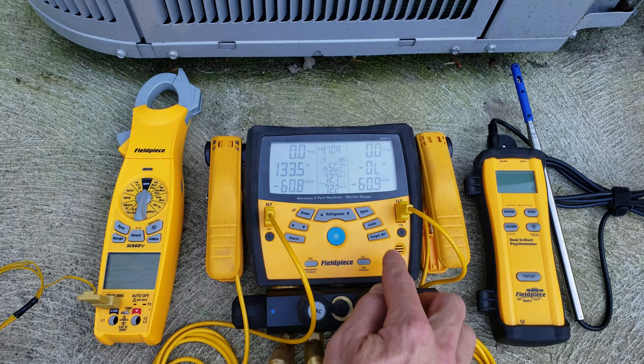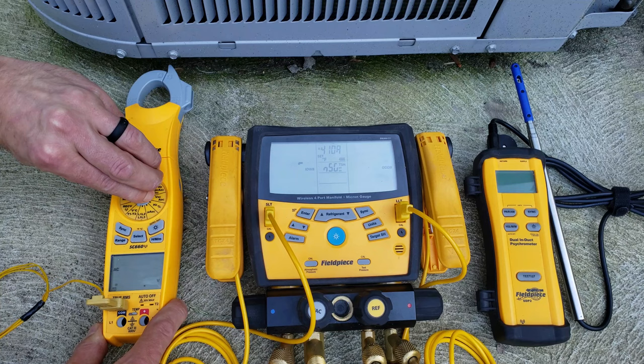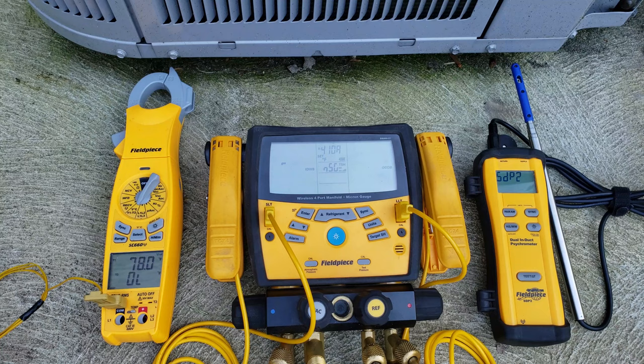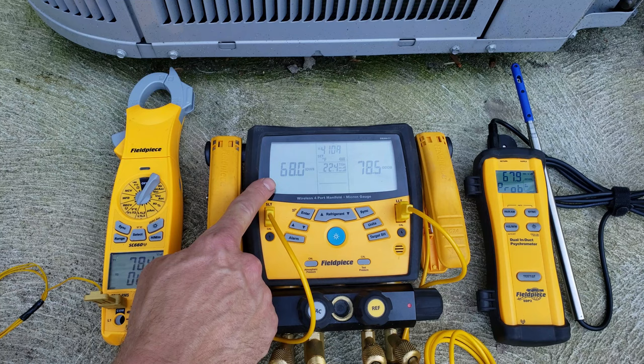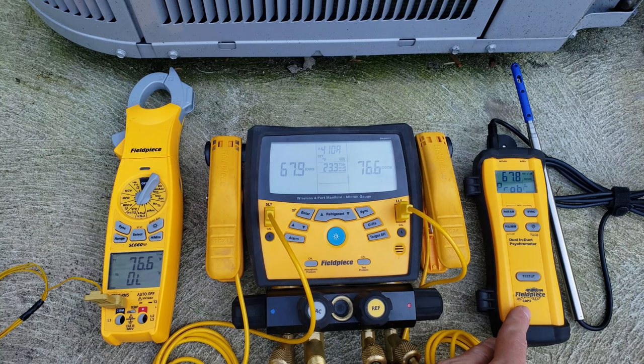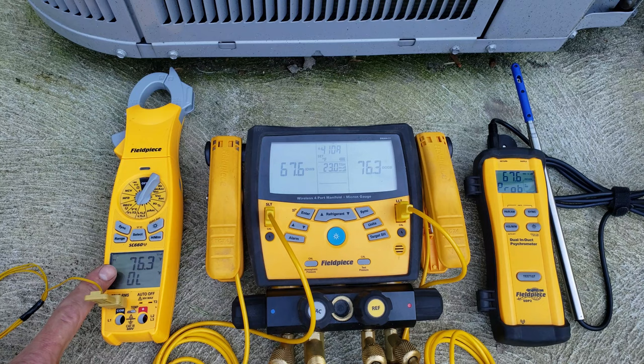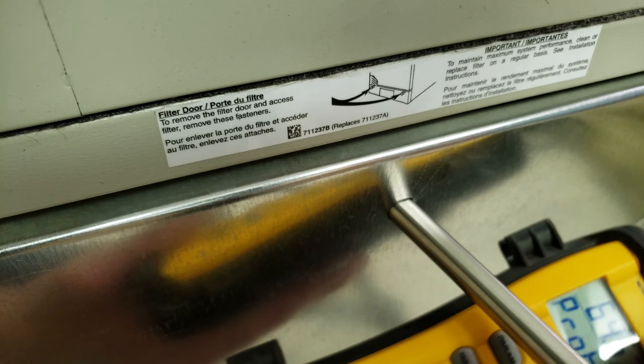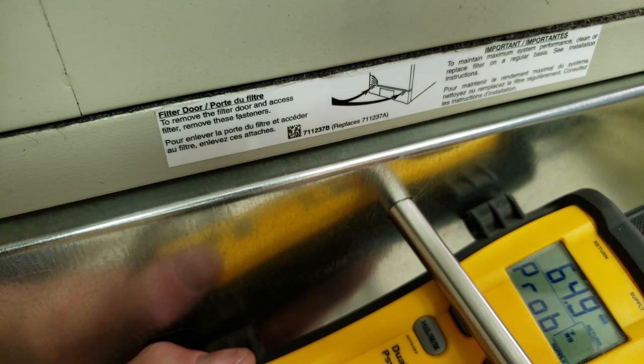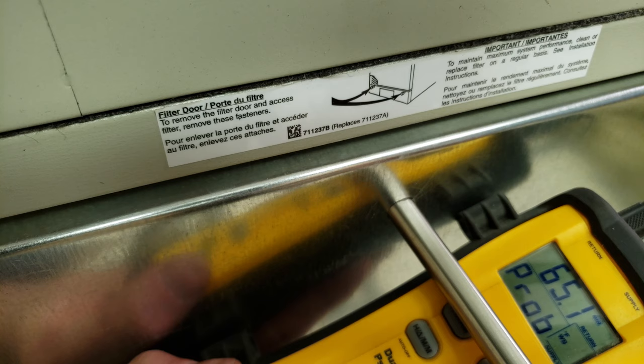Here we are outside with our digital manifold gauge set, and we need to determine what our target superheat is. Our manifold should recognize these other wireless tools here. You see our indoor wet bulb that's flashing right now, and it should come up. So we have 67.9, but I'm going to take this inside to our return. We have our outdoor dry bulb temperature, which we're going to measure about a foot away from the grill here. Here's our induct dual psychrometer. I only have one sensor on this right now, and this one will transmit a wireless wet bulb temperature out to the digital manifold set, such as the S-Man 460 or S-Man 480.